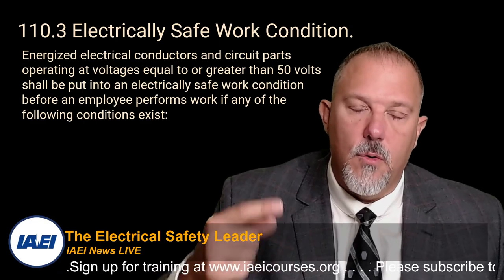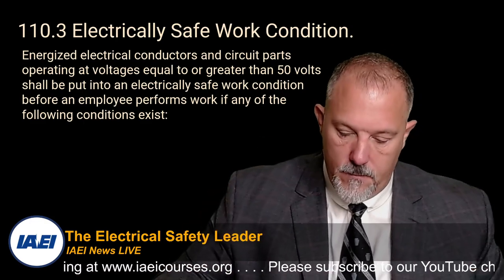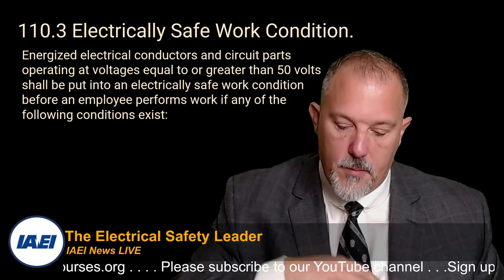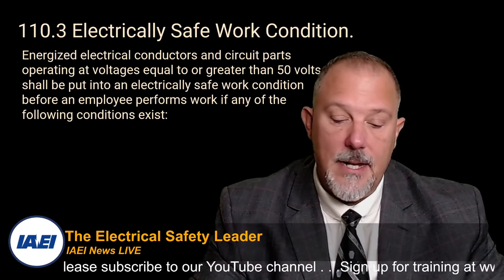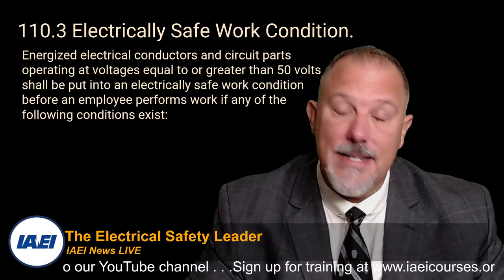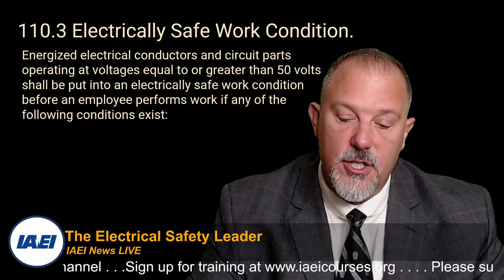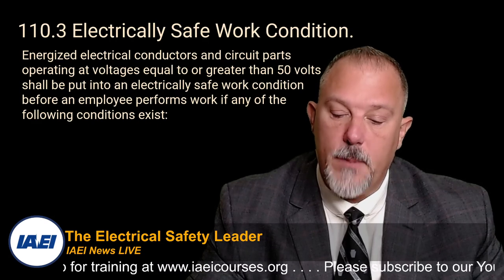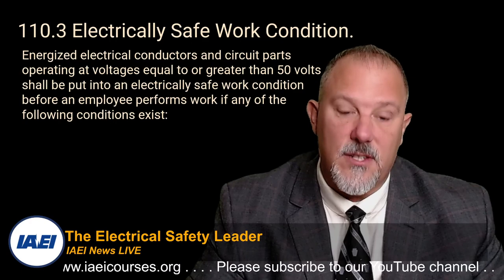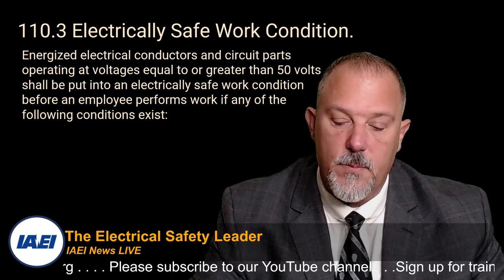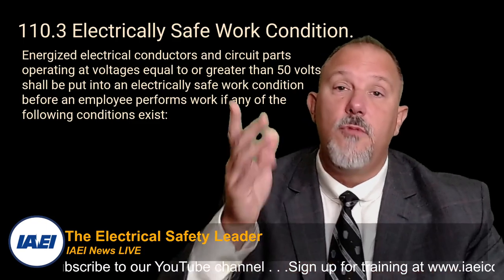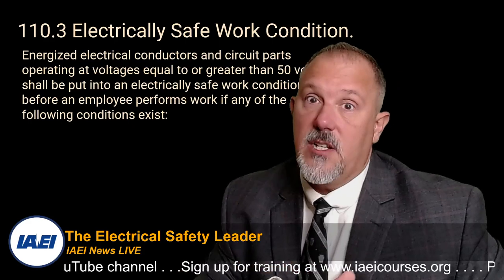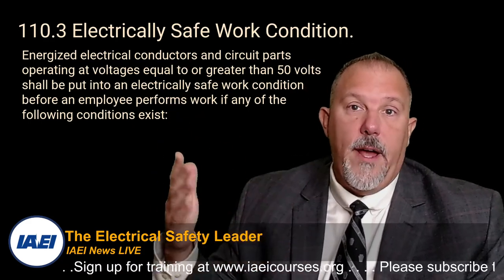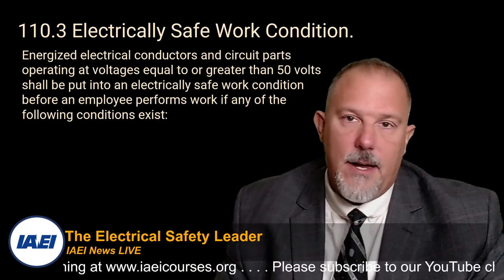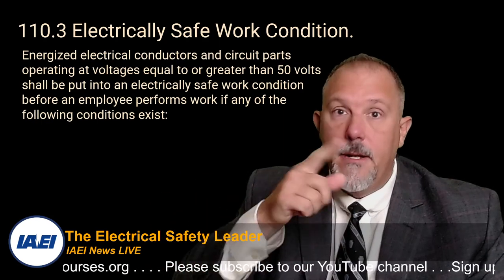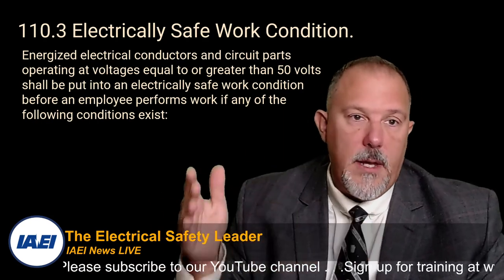So if I'm at 50 volts or more and I'm working based on 110.3, the employee is within the limited approach boundaries. The limited approach boundaries tell us, and if you look at Table 130.4(E)(a), the title of that table is Shock Protection Approach Boundaries to Exposed Energized Electrical Conductors or Circuit Parts for Alternating Current Systems. Less than 50 volts is not specified for exposure to movable conductors or fixed conductors. What's an example of a movable conductor? I think your best example is overhead lines, right? When you have, say, a service conductor that's coming down to a facility, connected at both ends but disconnected in between, and if it's exposed, then it could be a moving part.